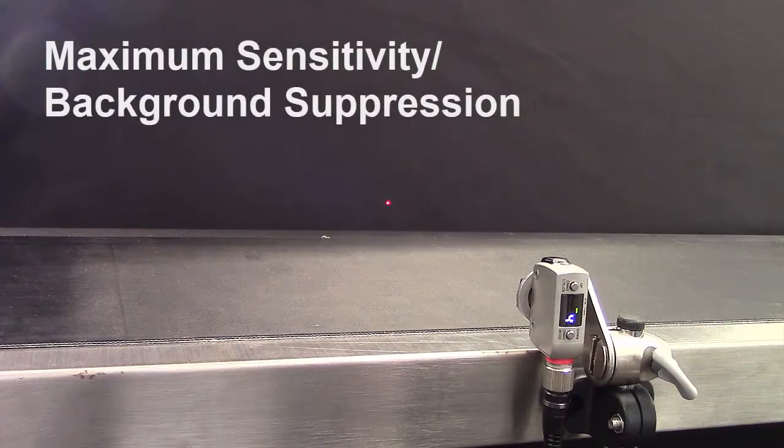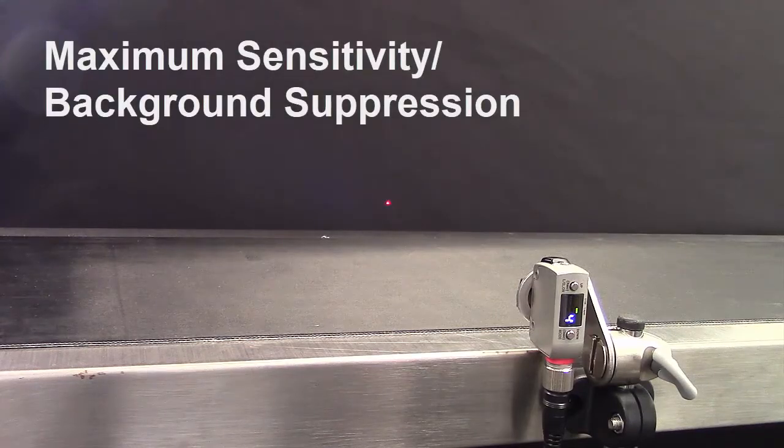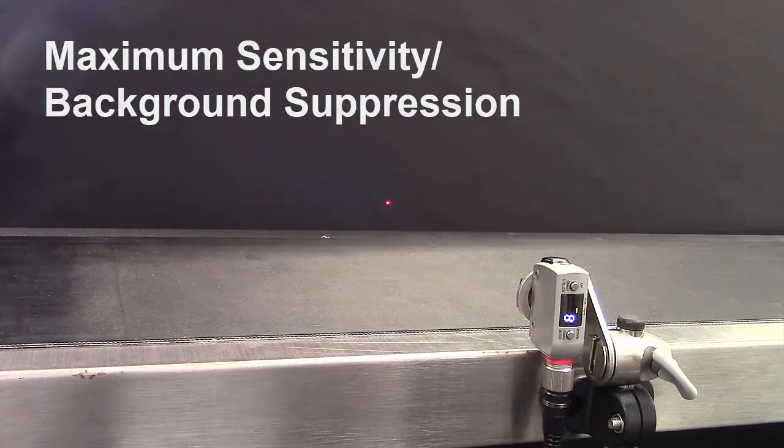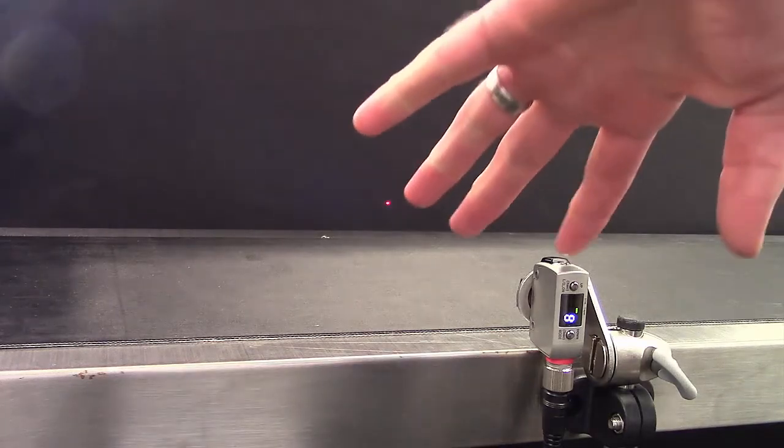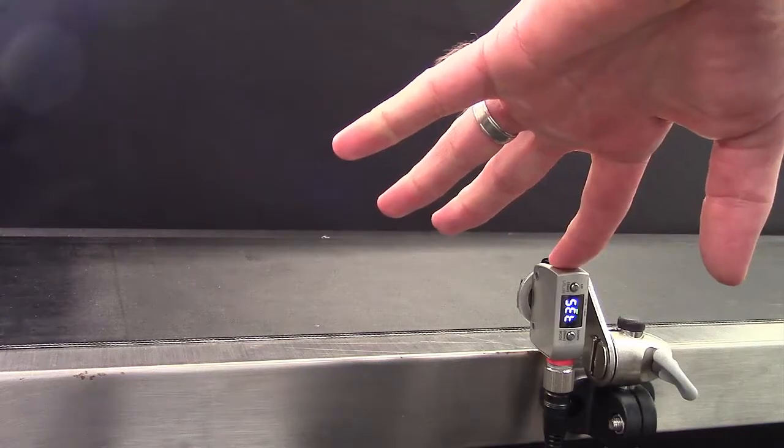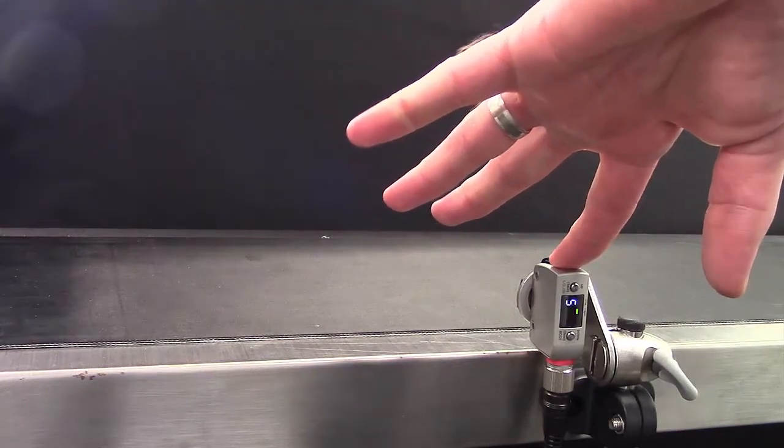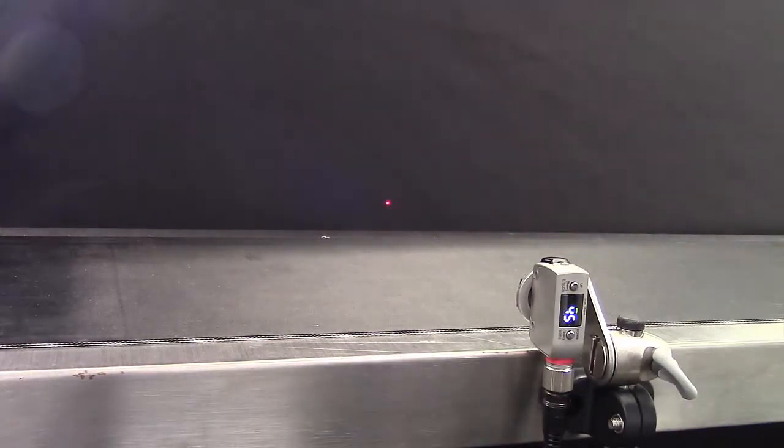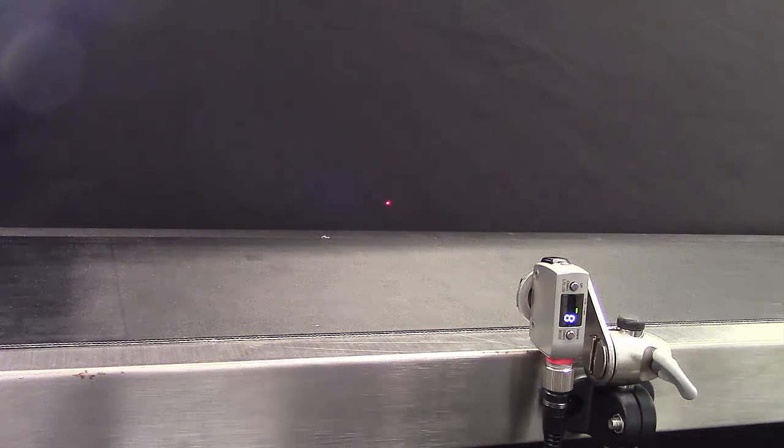Maximum sensitivity calibration, also known as background suppression calibration. This is easily achieved with a one-touch teach. Simply hold the set button for three seconds. It will detect the background and the sensor now detects anything in the foreground as a part.